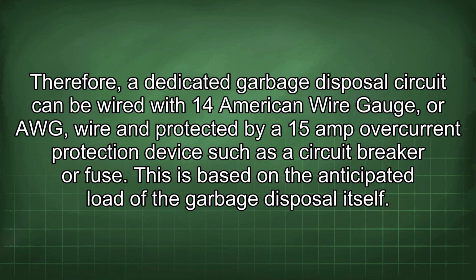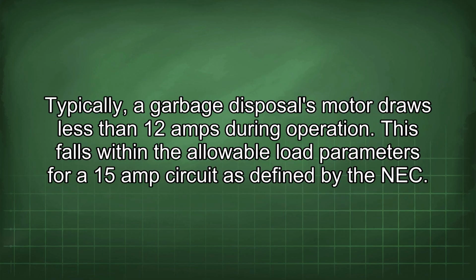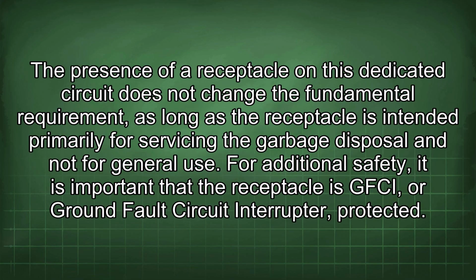This is based on the anticipated load of the garbage disposal itself. Typically, a garbage disposal's motor draws less than 12 amps during operation. This falls within the allowable load parameters for a 15-amp circuit as defined by the NEC. The presence of a receptacle on this dedicated circuit does not change the fundamental requirement, as long as the receptacle is intended primarily for servicing the garbage disposal and not for general use.